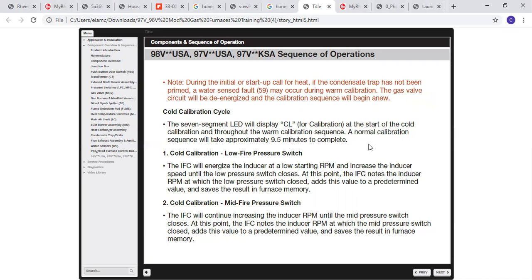One is a cold calibration. That's where it's running through the sequence, but it's not actually firing. During the cold calibration for the low fire pressure switch, the control board will energize the inducer at a low starting RPM and increase the motor until the low pressure switch closes. At this point, the IFC notes that RPM, saves it in the memory, adds the value to the predetermined value, and saves that result in the furnace memory.